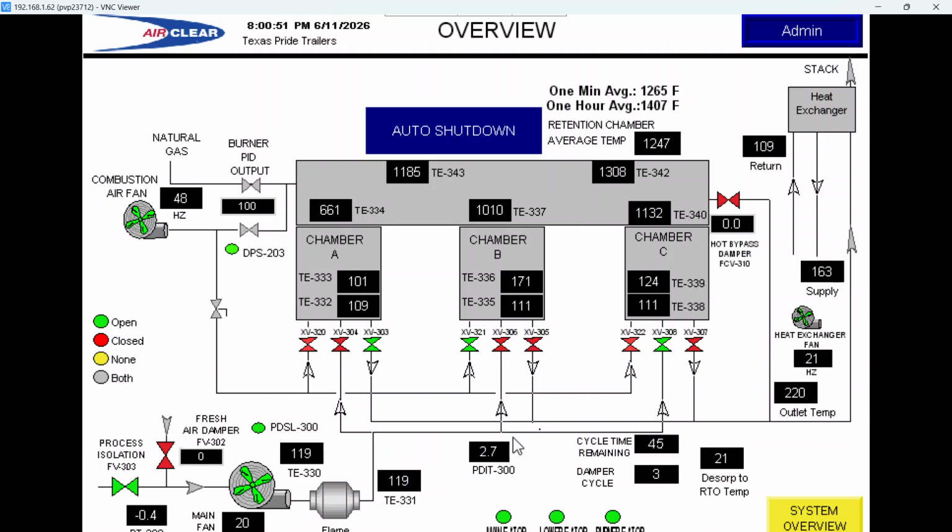So this thing is a big heat exchanger. The air comes in the chamber, it's preheated, it's heated by the burner the rest of the way when the burner's on, and comes through this chamber and heats up this medium. Okay? When this chamber goes onto an inlet, that hot media preheats the coming air. So this cycling of the chambers, these heat exchanger canisters or chambers, and the pockets, it's a heat exchanger.